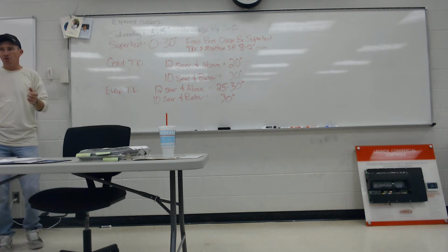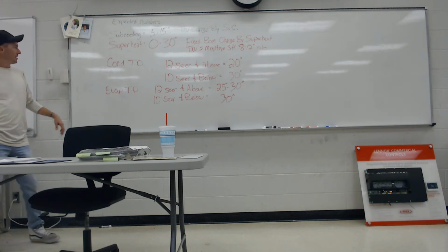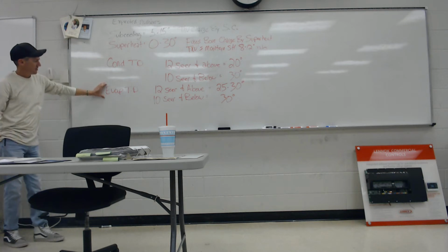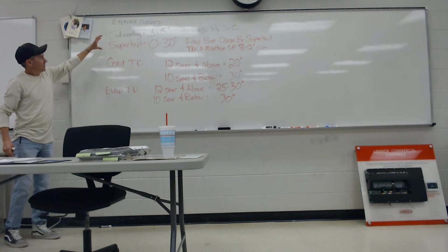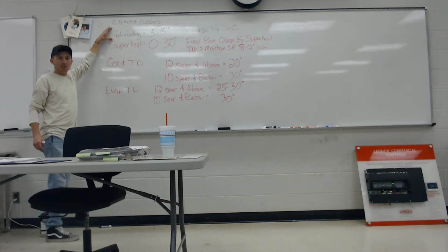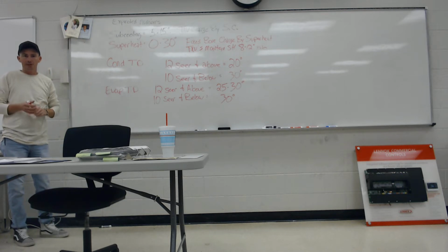As soon as you hook up, is my head pressure okay? Is my suction pressure okay? How much liquid is in my evaporator? Is superheat okay? How much liquid is in my condenser? That's the name of the game. Where's the refrigerant at? Where's the refrigerant at?